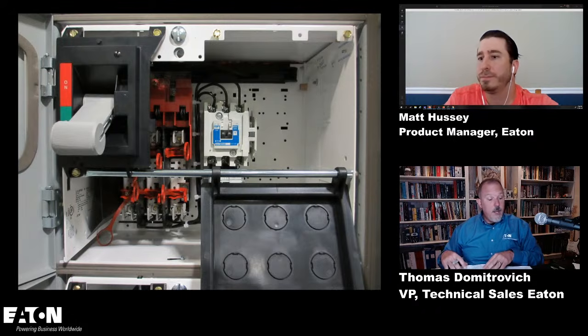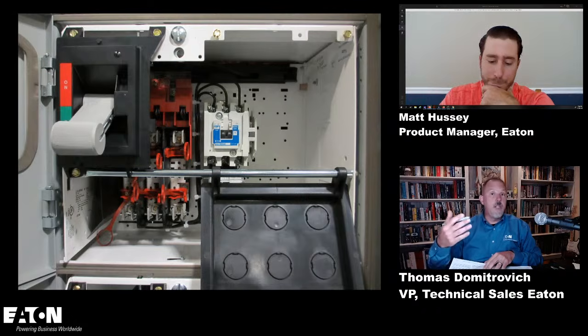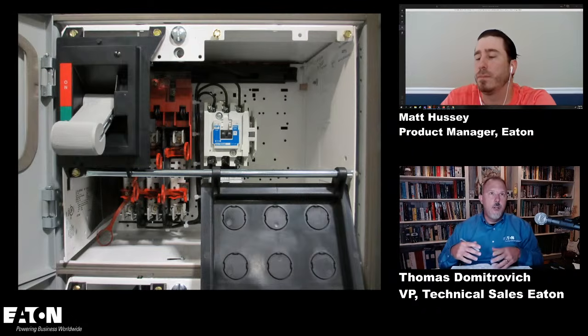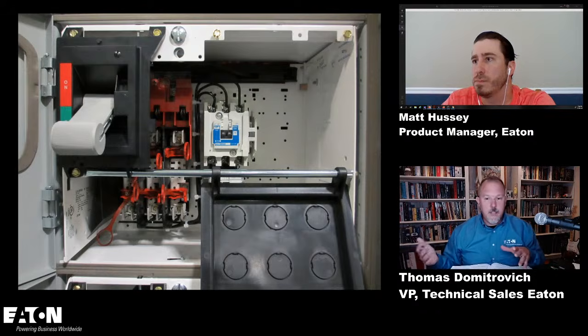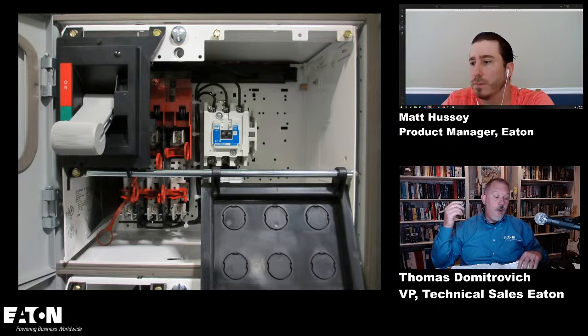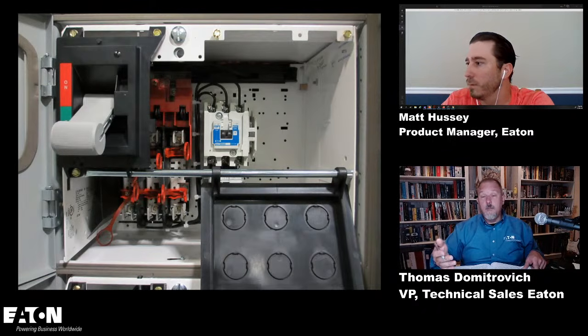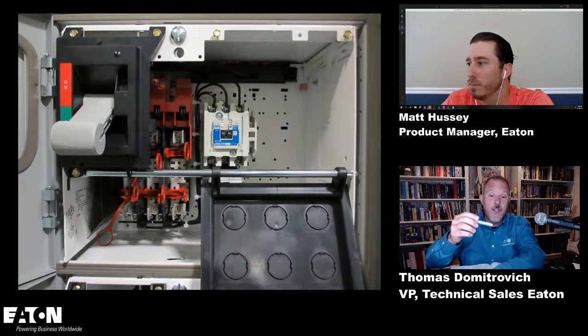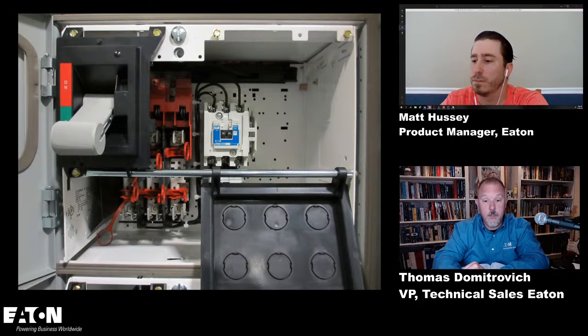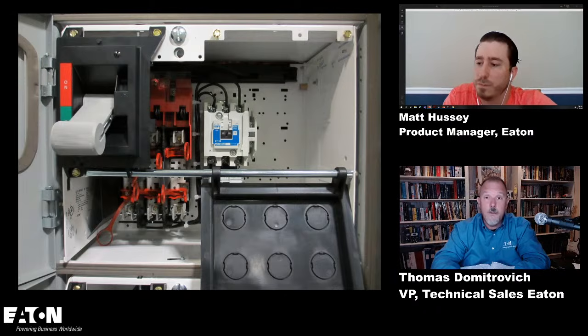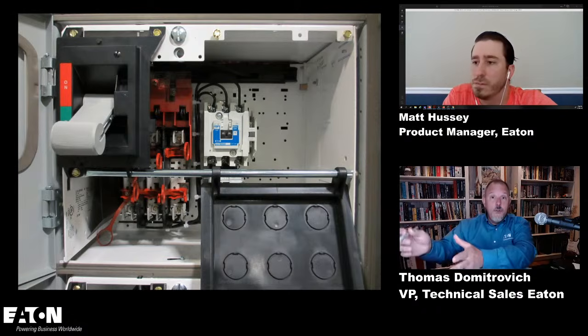That's right. Now, in the National Electrical Code, there's no place that says it has to be a listed motor control center. It has to be a listed bucket. It has to be a listed motor. There's no requirement. The circuit breakers don't even have to be listed. There are products and solutions that are required to be listed, but what AHJs will use is that listing mark so that they don't have to look at every one of those components. If it's not a listed product, they're going to have to figure out how to consider whether the short circuit current rating of the equipment is adequate and all that good stuff. So it puts them in a difficult position with regard to approving something.